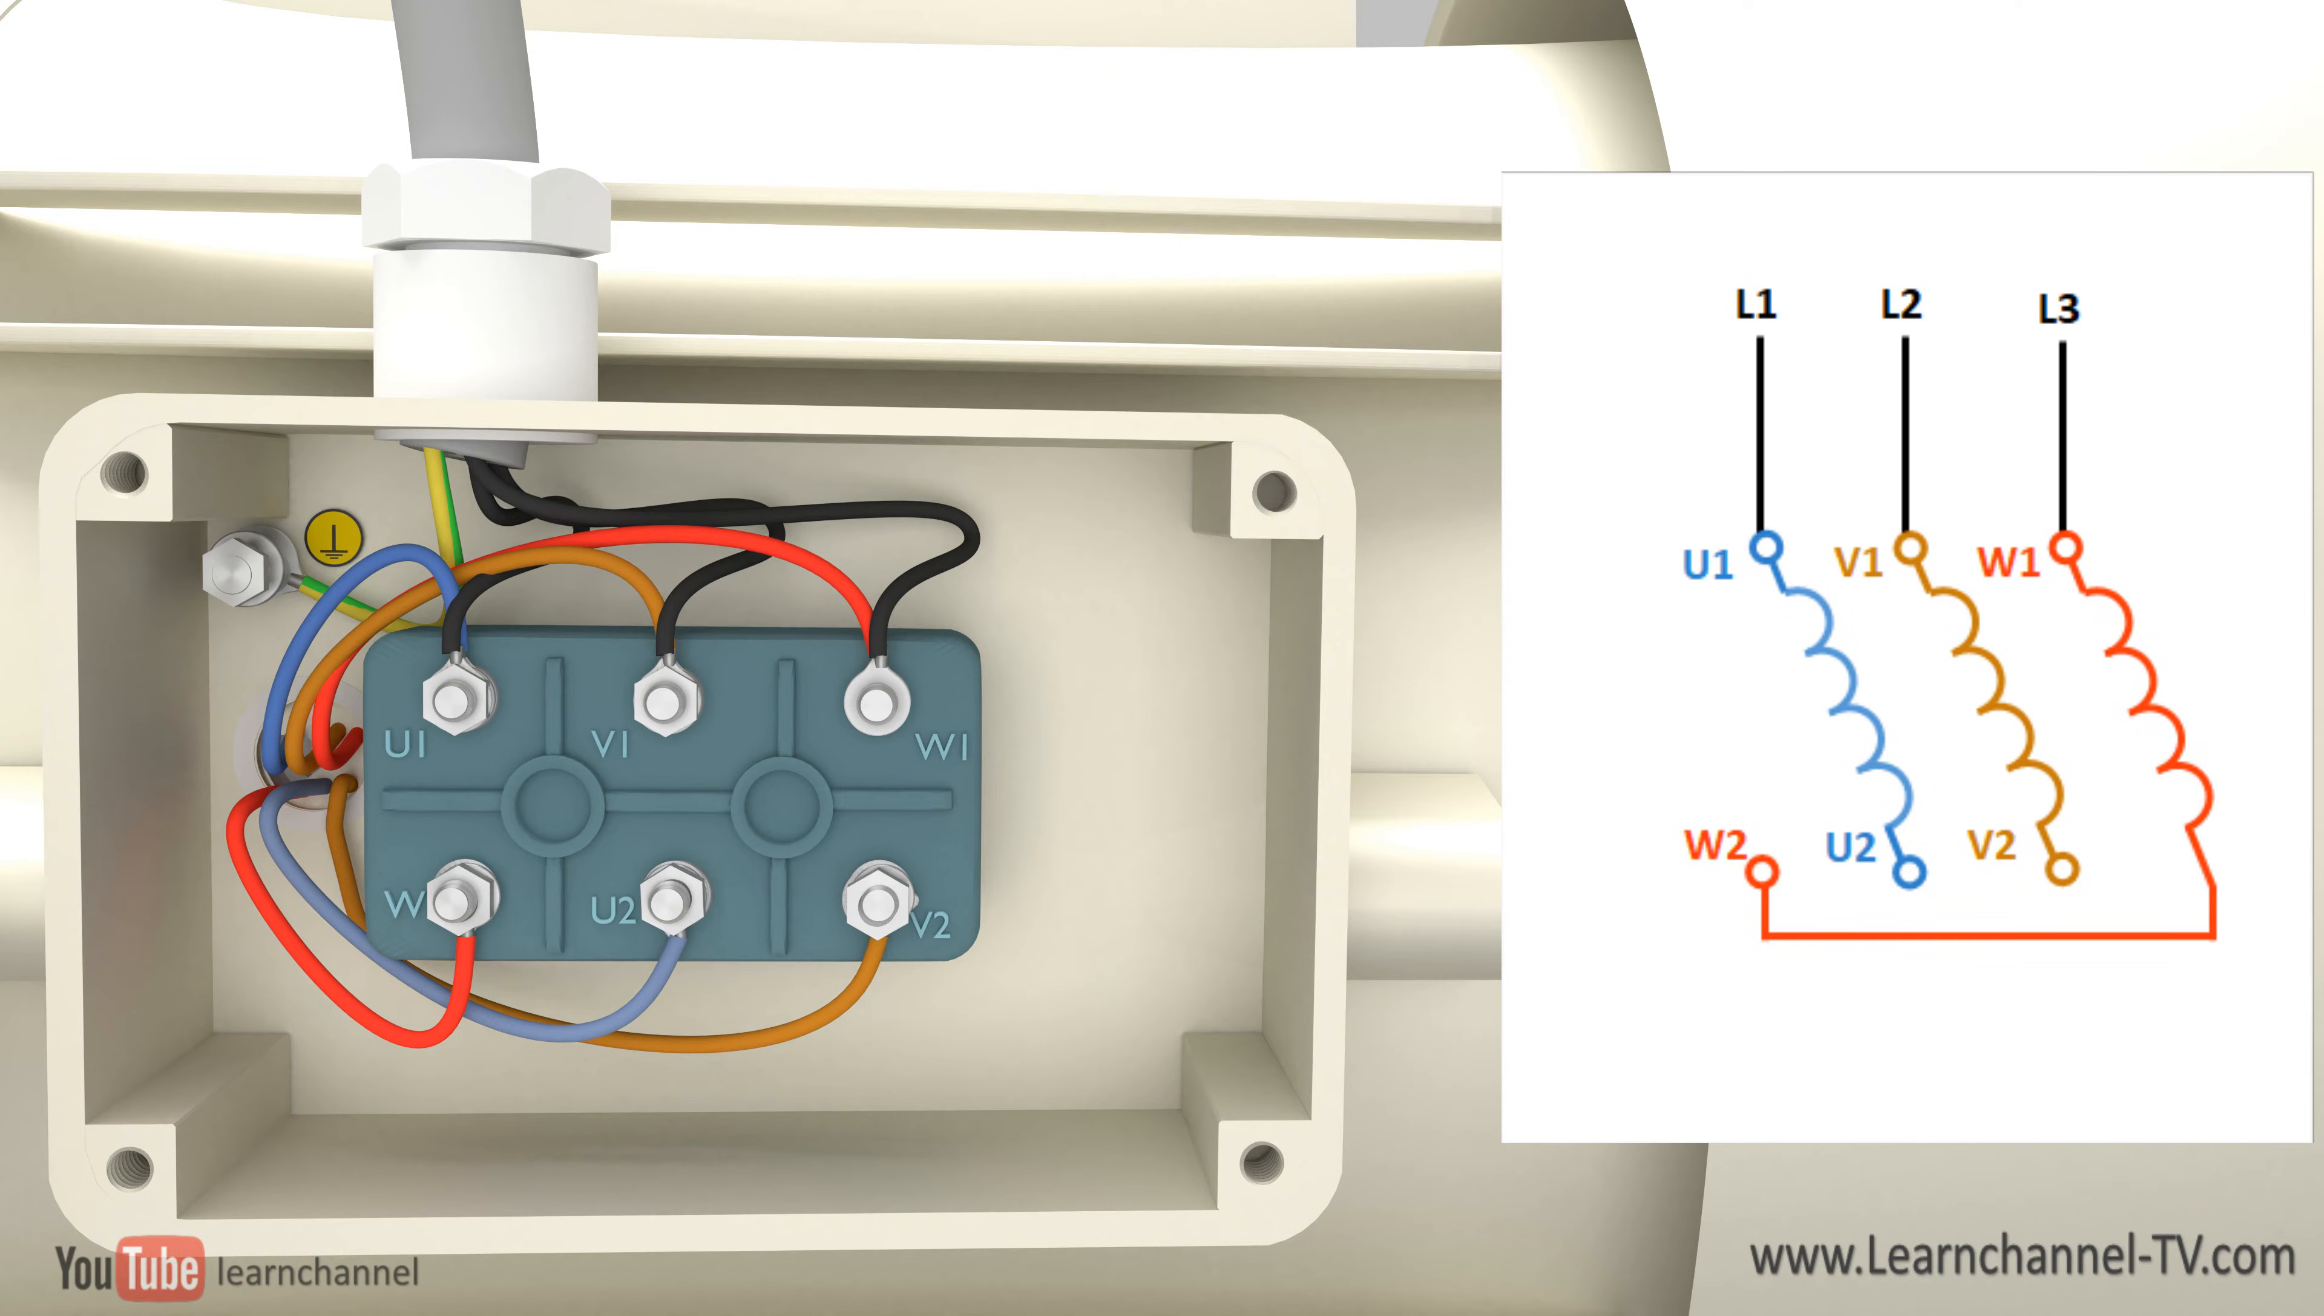In the motor terminal board, it can be determined whether the motor runs in star or in delta. In star, the ends of the windings are connected to each other. In delta, on the other hand, the end of one winding goes to the beginning of another winding.